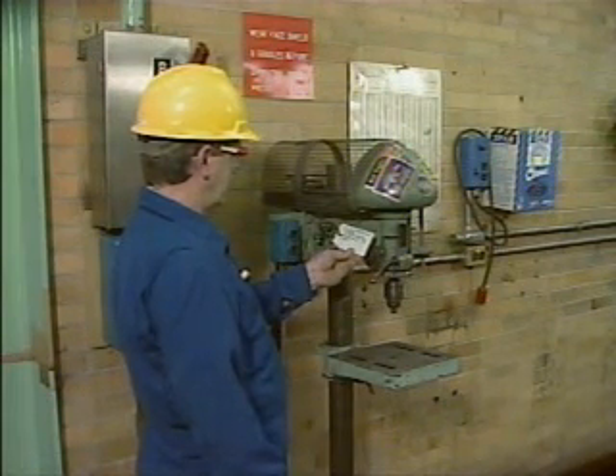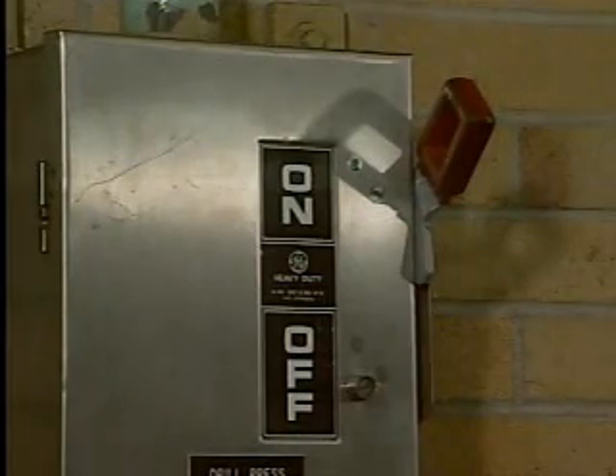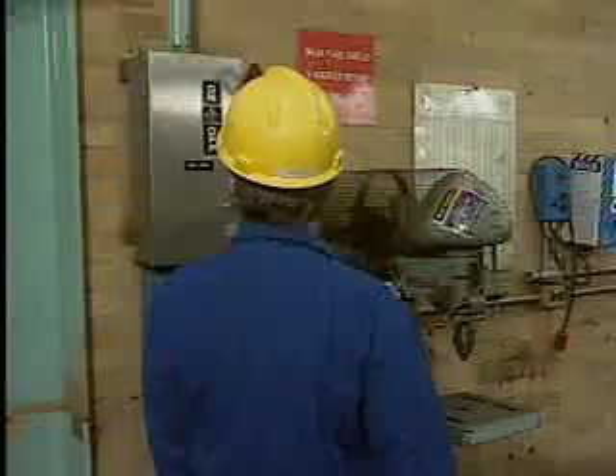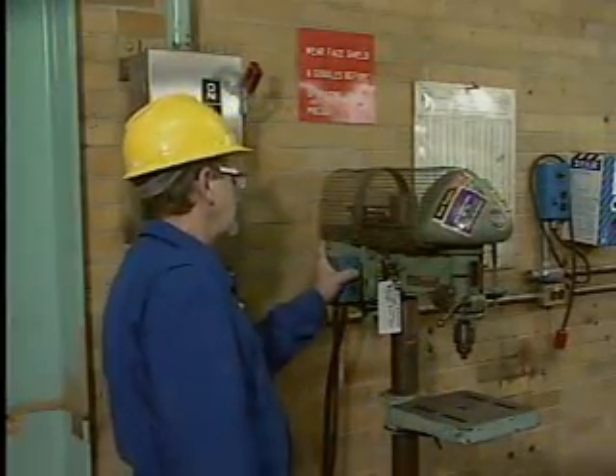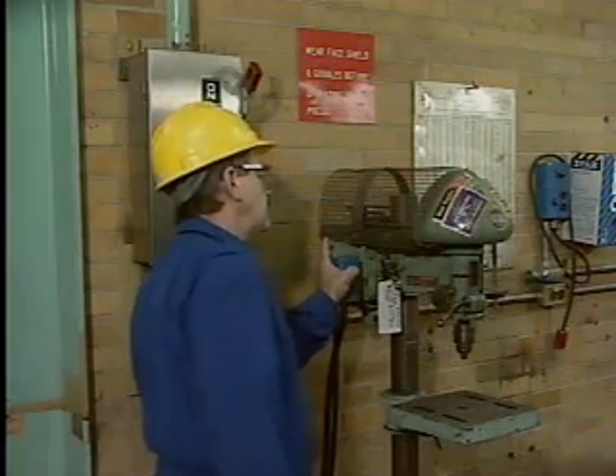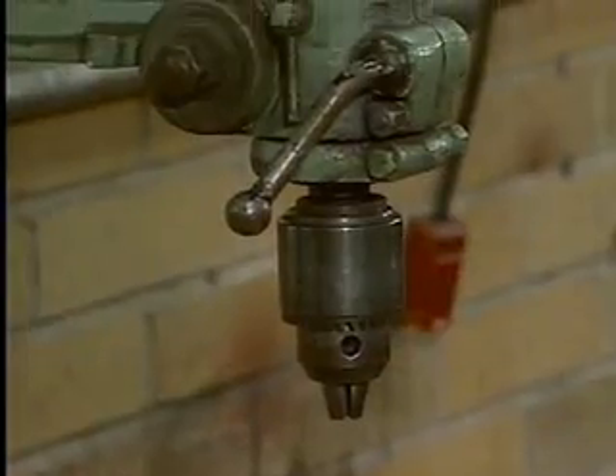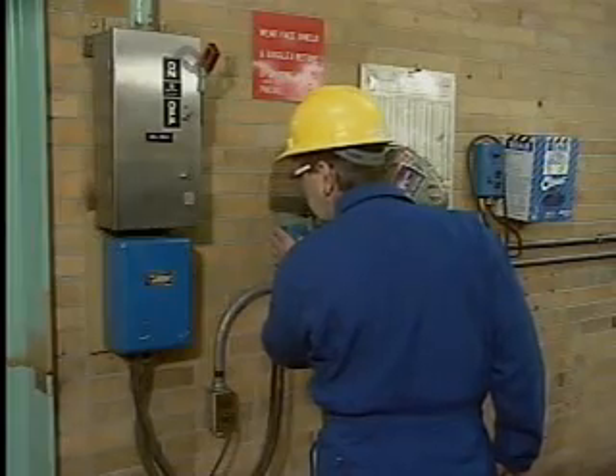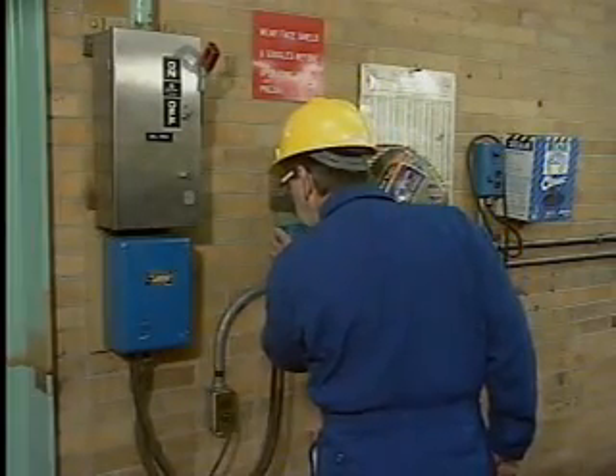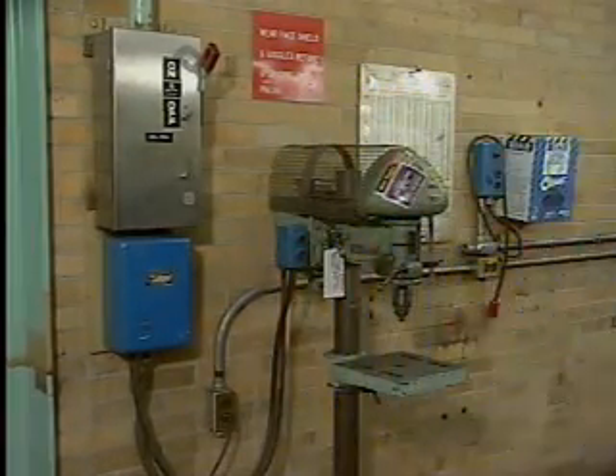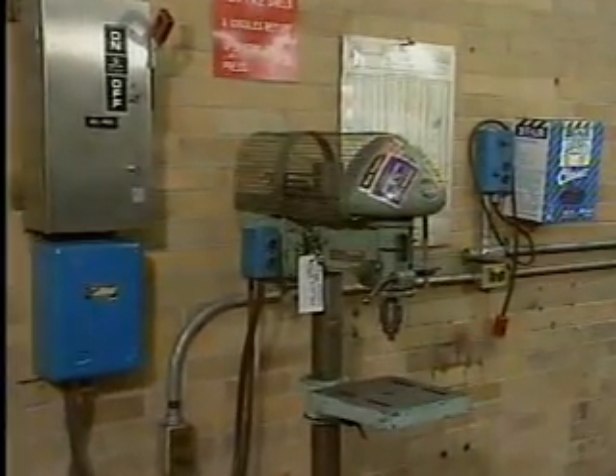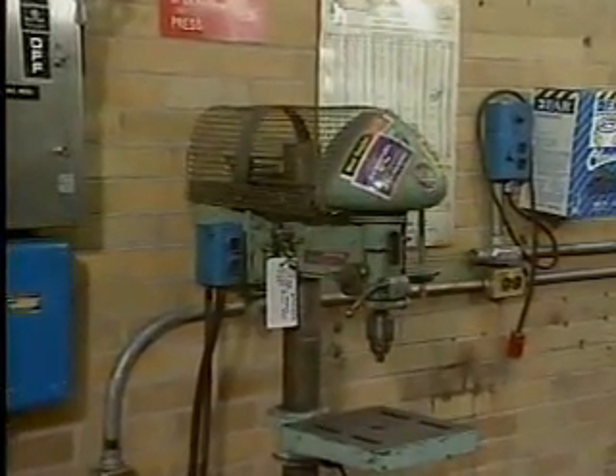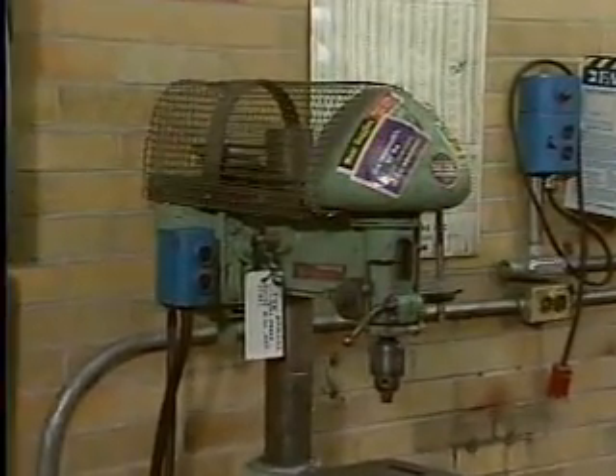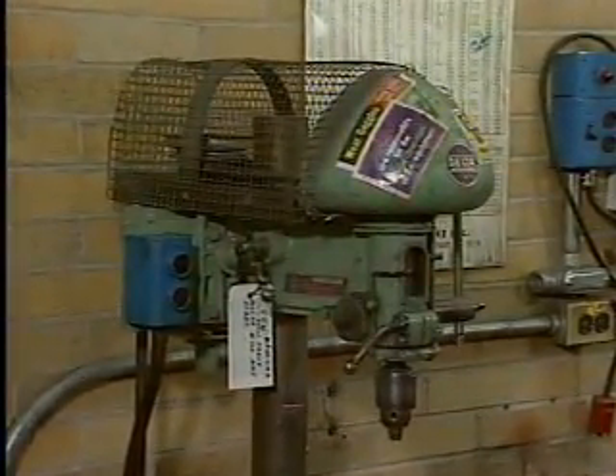He also sees that a tag has been placed on the drill to tell others that the drill press doesn't work properly. After making sure that the power switch on the fuse box is in the on position, the electrician tries to start the drill to verify that the actual problem is the same as the reported problem. The drill does not start, nor does it seem like any part of the drill or its motor is trying to start. In addition, the electrician does not hear the relay in the control cabinet making contact. At this point, the problem identified by maintenance shop personnel and confirmed by the electrician is that the drill press does not operate properly. Specifically, the drill press will not start.